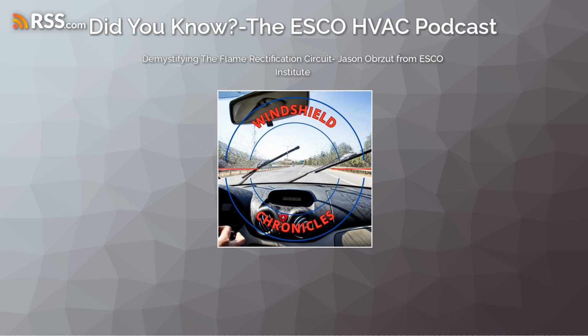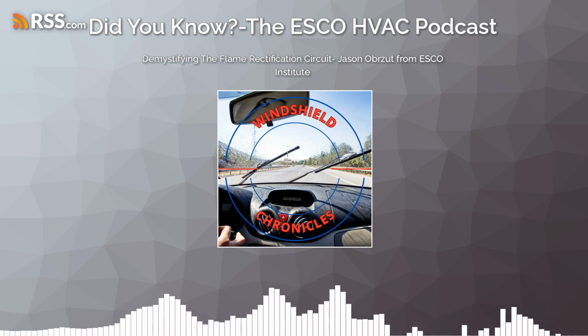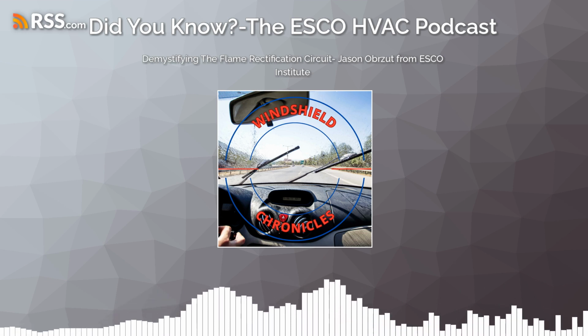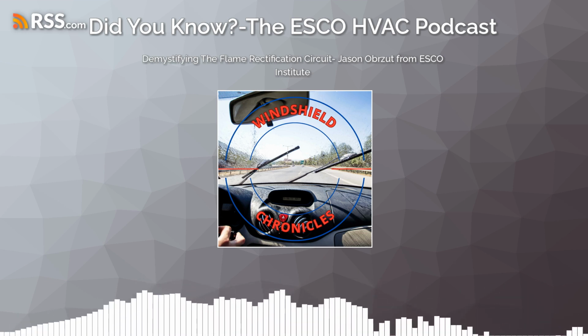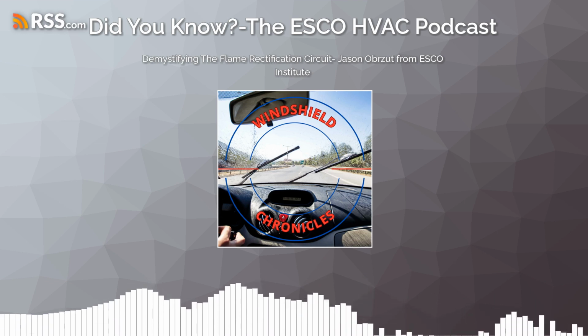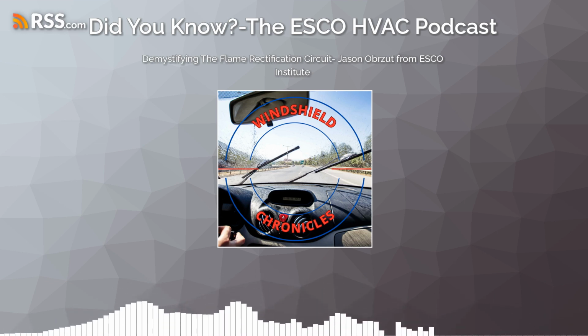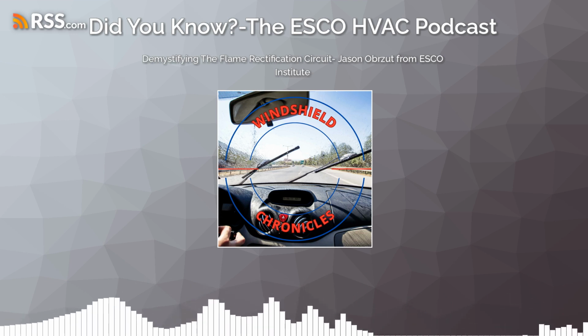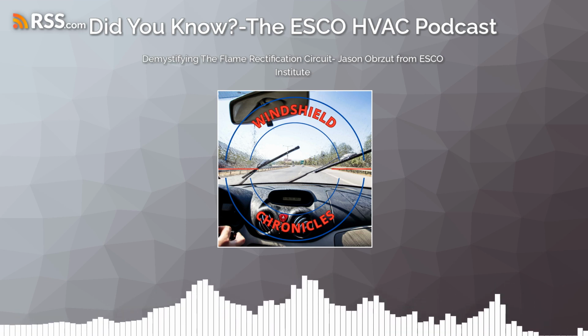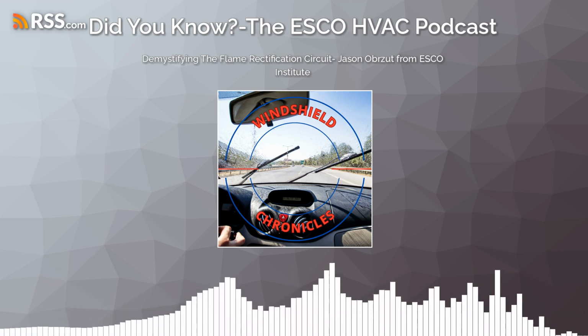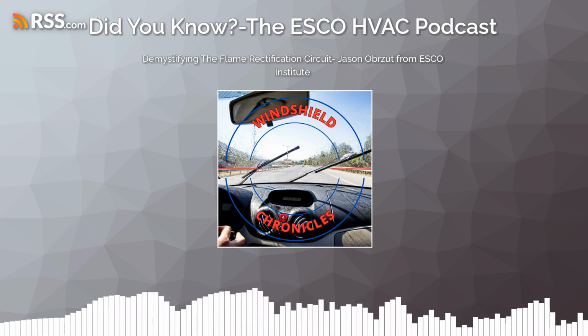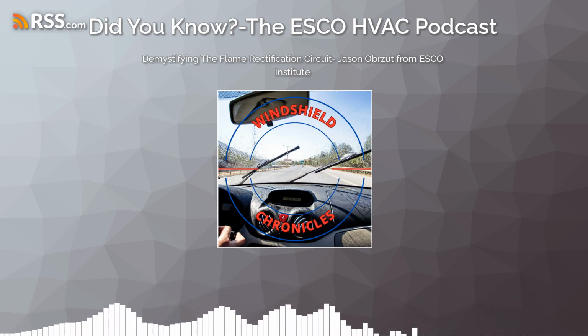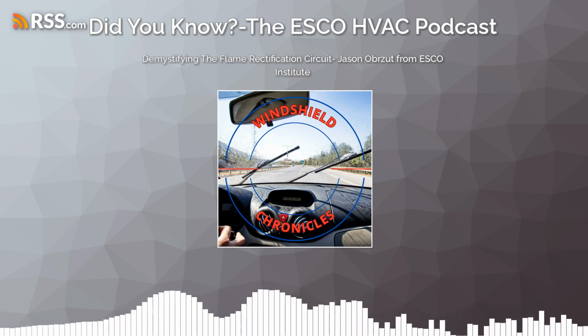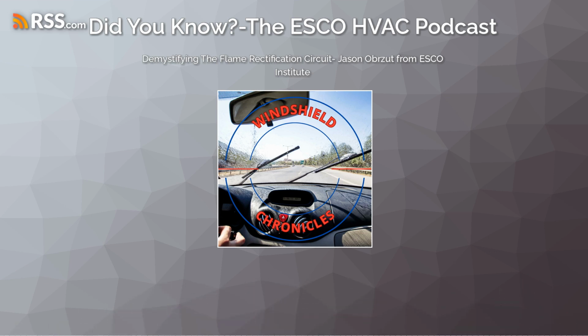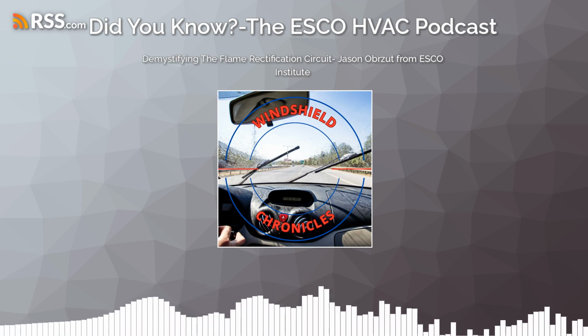So let's think about this electrically, right? Just so we can see what's going to happen. If we think about this electrically, that means we're applying an AC voltage. We are going to convert into a DC looking signal, only because that's what happens in the ionization side. And so our meters can't read it as AC anymore. It's not a clear path to ground. Remember, we're jumping through flame. We're jumping across carbon atoms and water molecules. And we're going through this effective ionization that's in the flame. We don't have a straight path to ground. So our meter can't read AC. It reads it as DC.